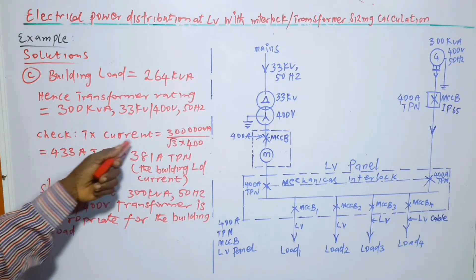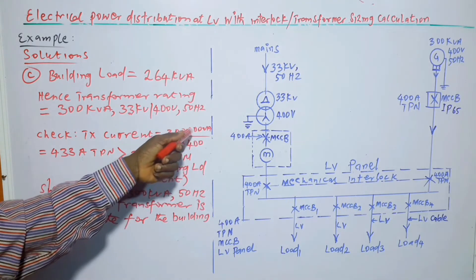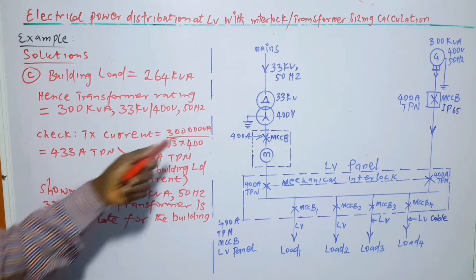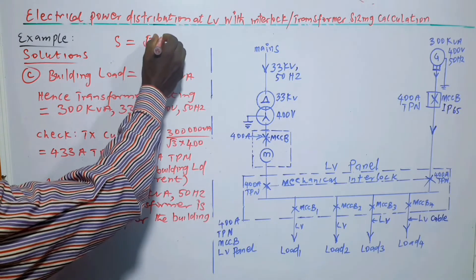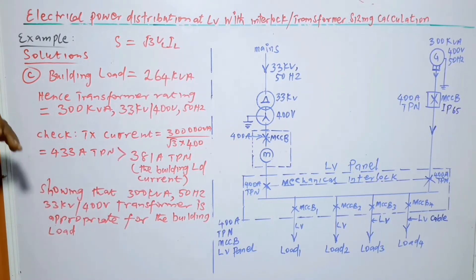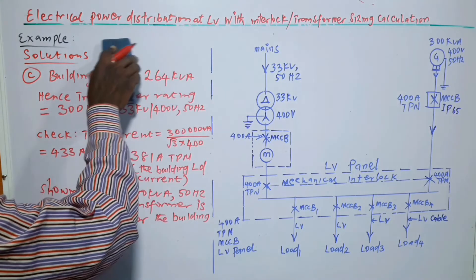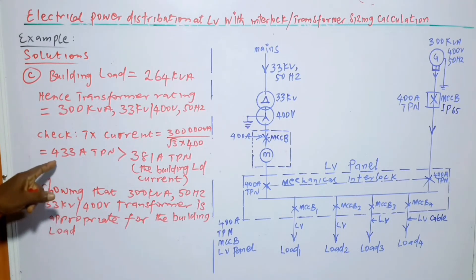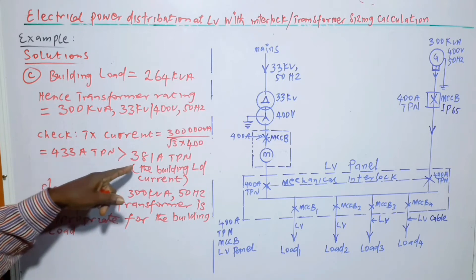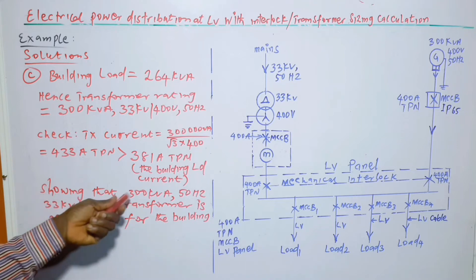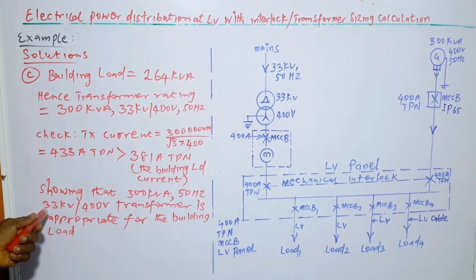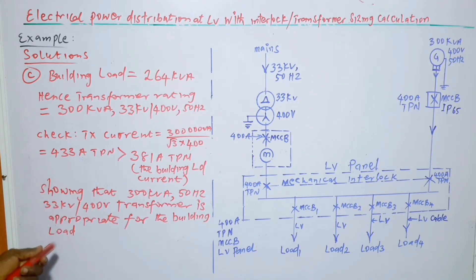Then we can check what the transformer current is: 300 kVA or 300,000 VA divided by root 3 times 400. From the apparent power formula, S is equal to root 3 V line I line. So from there we can calculate the current. If it is correctly calculated, the answer is 433 ampere three-phase with neutral, which is greater than the load current calculated in part B. And that is showing that 300 kVA at 50 Hz with 33 kV on the primary side and 400 volts on the secondary side transformer is appropriate for the building load. And that is the answer to part C.